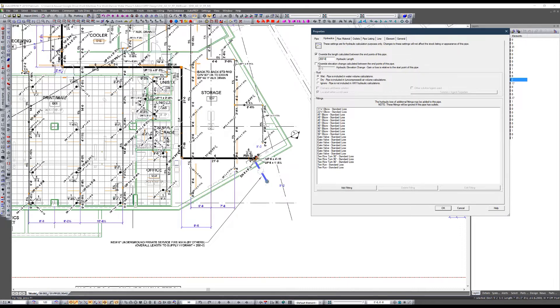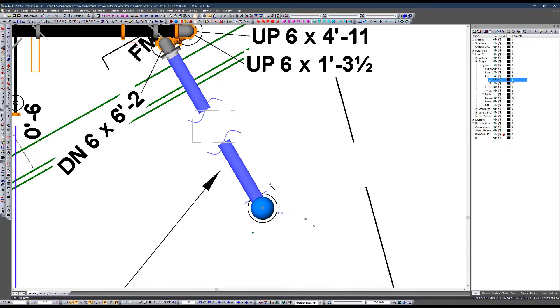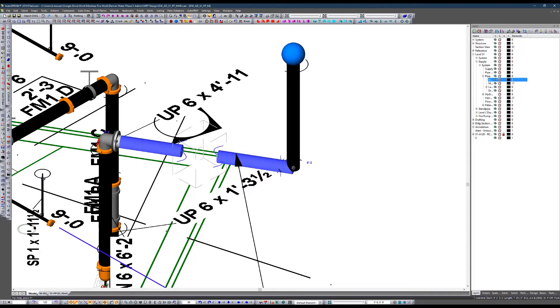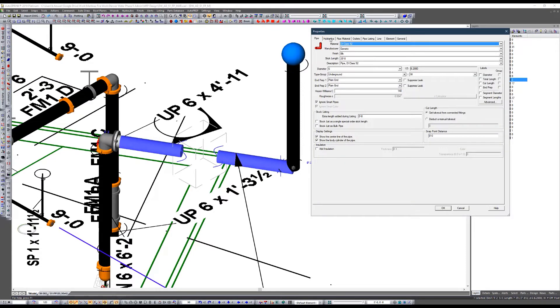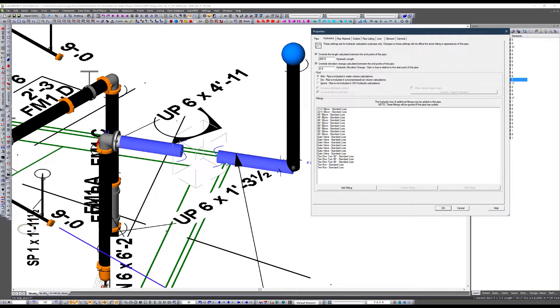The one thing I did not do was override the elevation change. This is where you tell the program to gain or lose elevation relative to the start point of the pipe, which is why the direction the underground pipe is drawn is critical. Here I'm telling the program that I'm gaining six feet from the start point to the end point of this pipe segment across 200 feet, so the program will show a six-foot elevation gain.